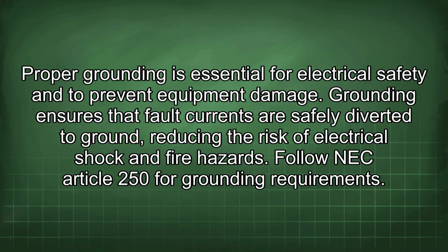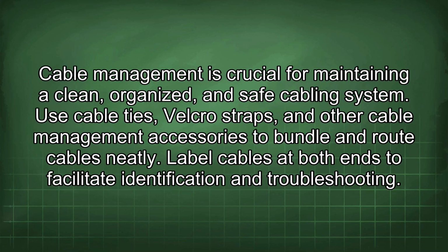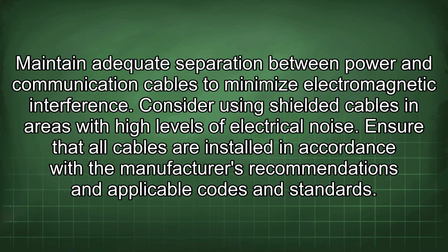Proper grounding is essential for electrical safety and to prevent equipment damage. Grounding ensures that fault currents are safely diverted to ground, reducing the risk of electrical shock and fire hazards. Follow NEC Article 250 for grounding requirements. Cable management is crucial for maintaining a clean, organized, and safe cabling system. Use cable ties, Velcro straps, and other cable management accessories to bundle and route cables neatly. Label cables at both ends to facilitate identification and troubleshooting. Maintain adequate separation between power and communication cables to minimize electromagnetic interference. Consider using shielded cables in areas with high levels of electrical noise.